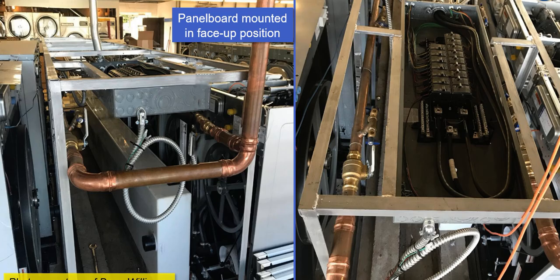because you do not have, from 110.26, your approved clearance in front of it. Your clearance should be at least 6.5 feet, I believe, in height, and at least 30 inches or the width of the equipment, whichever is greater. So a panel might be 14 inches wide, and if the equipment was wider than 30 inches, then it should be that width. The width of the equipment or 30 inches, whichever is greater.